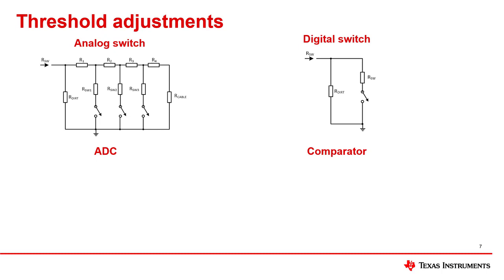After selecting which inputs would monitor ground connected switches, or supply connected switches, either ADC or comparator mode is selected, and then thresholds need to be pre-programmed so the MSDI can distinguish between open and closed switch states.